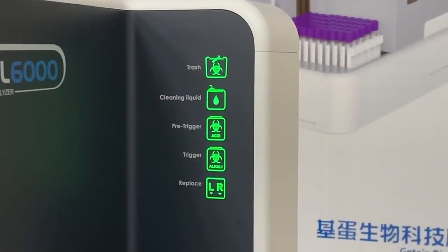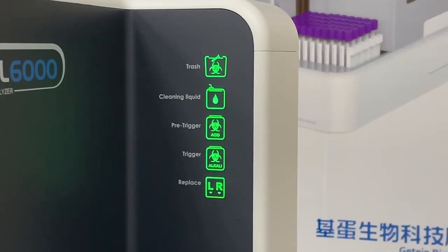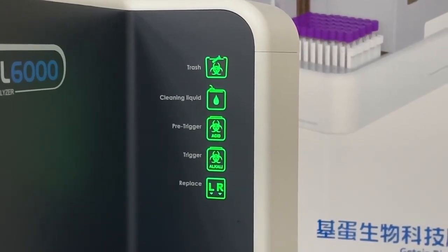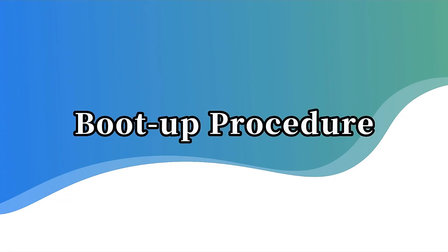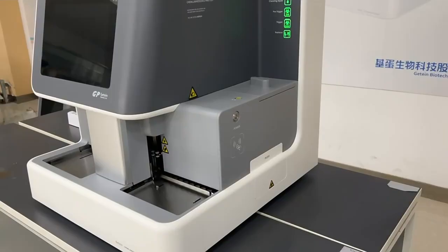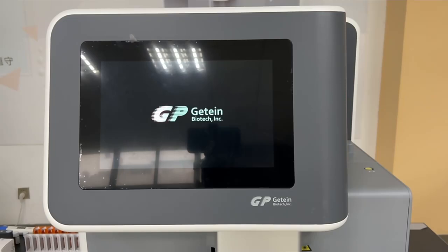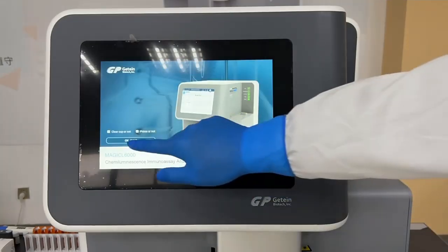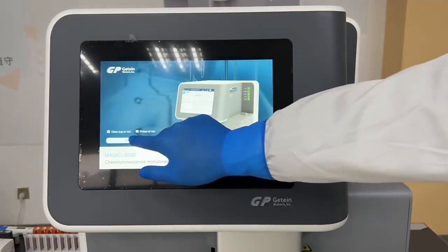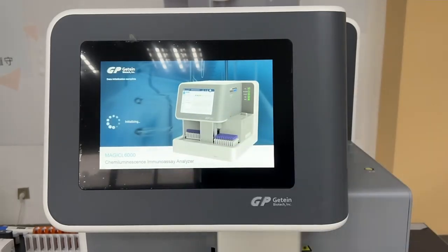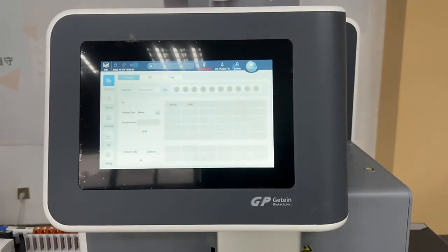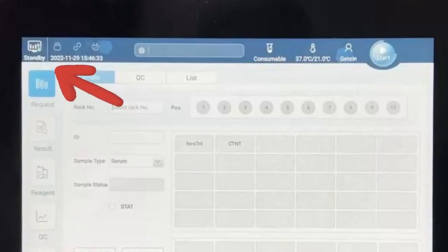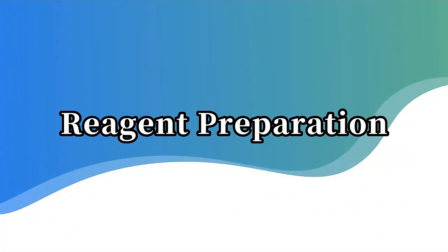Check the capacity of the waste container, the remaining volume of the cleaning tank assembly, and the activators 1 and 2. Boot up procedure. Turn on the main switch behind and press the power button on the right side. Click the OK button on the screen to enter the main screen. Wait for the machine to warm up. The machine cannot be operated when the small icon in the top left corner shows init or maintain status until it turns to standby.